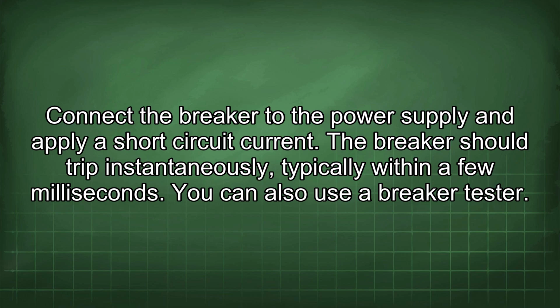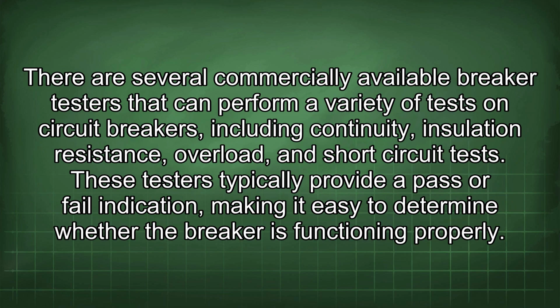You can also use a breaker tester. There are several commercially available breaker testers that can perform a variety of tests on circuit breakers, including continuity, insulation resistance, overload, and short circuit tests. These testers typically provide a pass or fail indication, making it easy to determine whether the breaker is functioning properly.